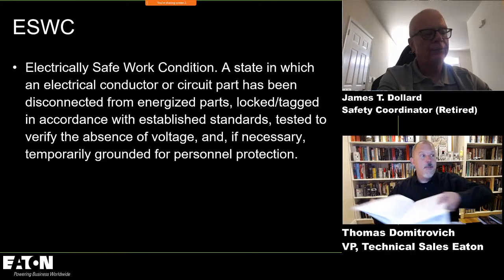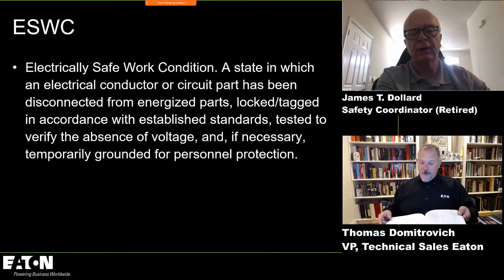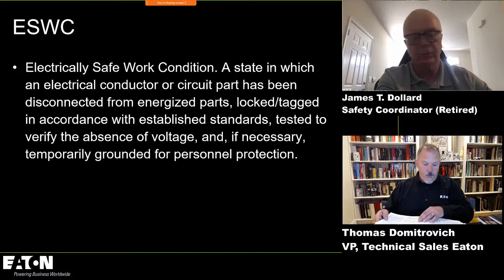Okay, so establishing. This is the definition of an electrically safe work condition, and the key here is for everybody to understand that an electrically safe work condition is a state. We have to create that state, and then we have to maintain that state. As long as we do that, we have an electrically safe work condition. So that's where we've got an energized motor control center, switchboard, or panel board. But what we do is that electrical conductor or circuit part is disconnected from energized parts, is locked and tagged in accordance with established standards, and those established standards are your employer's written lockout, tagout procedures.